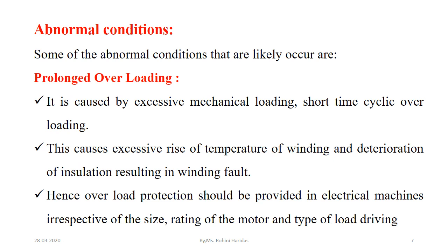Among abnormal conditions, the first is prolonged overloading, caused by excessive mechanical loading or short-time cyclic overloading. This causes an excessive rise in winding temperature and deterioration of insulation, resulting in winding faults. Hence, overload protection should be provided in electrical machines irrespective of the size, rating, and type of load.